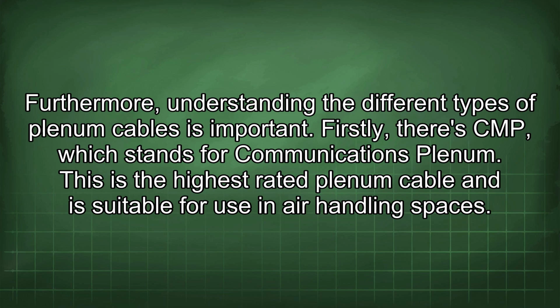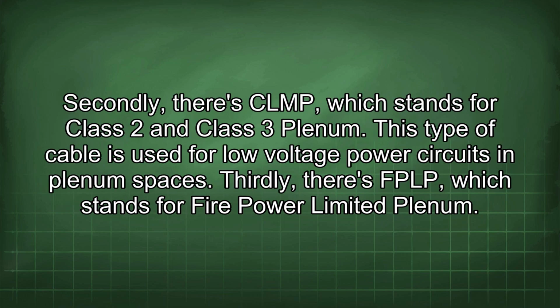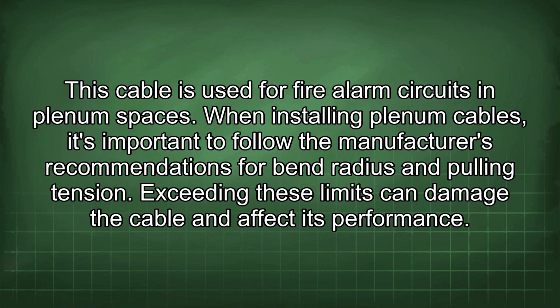Firstly, there's CMP, which stands for Communications Plenum. This is the highest rated plenum cable and is suitable for use in air handling spaces. Secondly, there's CLMP, which stands for Class 2 and Class 3 plenum. This type of cable is used for low voltage power circuits in plenum spaces. Thirdly, there's FPLP, which stands for Fire Power Limited Plenum. This cable is used for fire alarm circuits in plenum spaces.